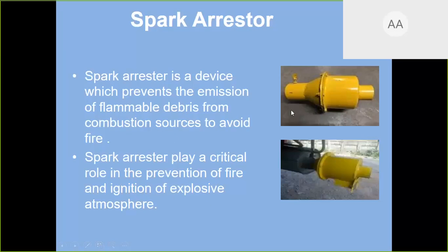So this yellow colored instrument, this is a duct which is going. There is a flange. I open the flange, put this spark arrestor in and close it with the flange, and then my operation is running. The duct is running, dust is going to the dust collector, but this spark arrestor will ensure that from this machine, no ignition source goes to my dust particles, which have been collected from the machine. So the spark arrestor will also prevent the fire if it is installed and maintained.